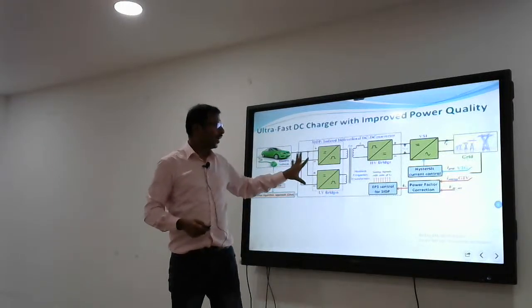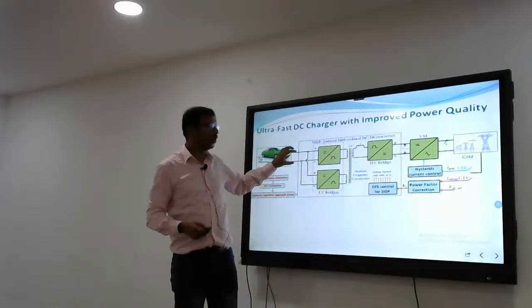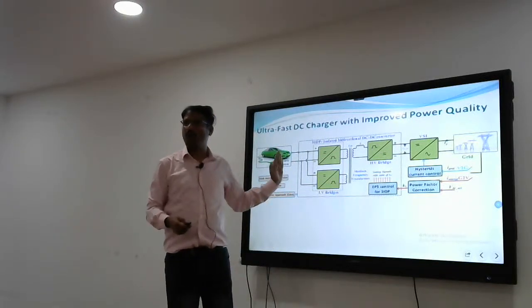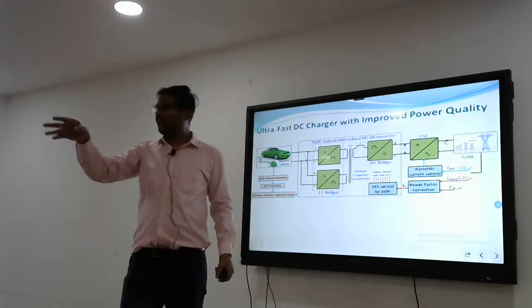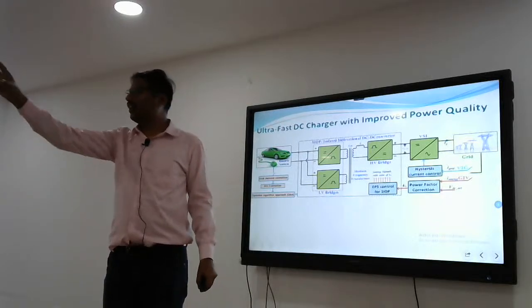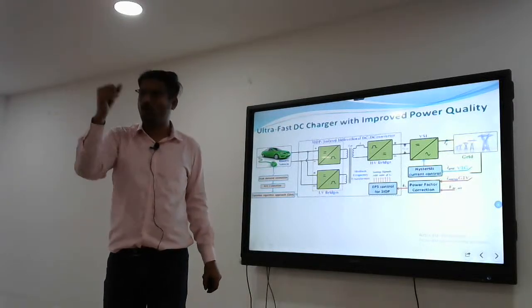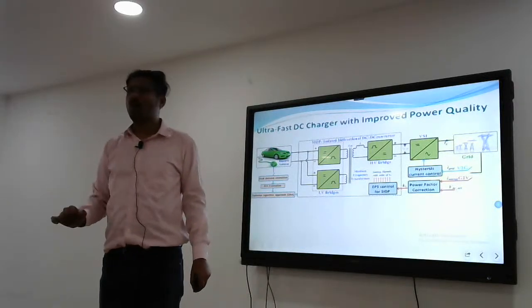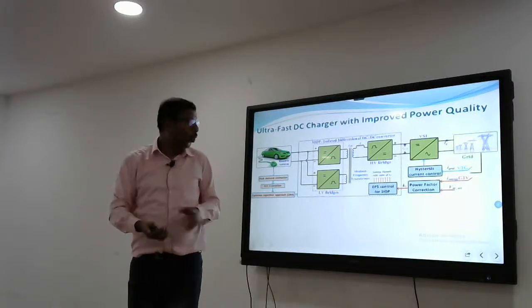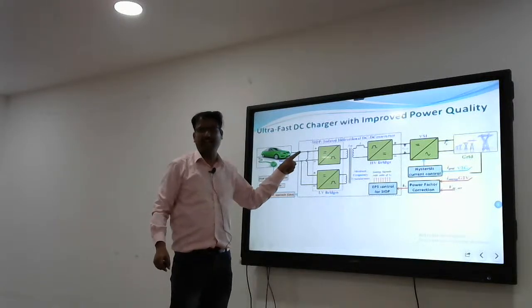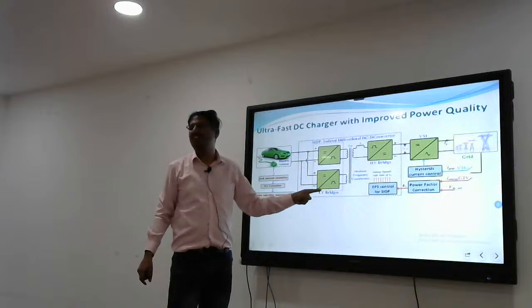This is actually such that one end becomes high voltage, the other end becomes low voltage, but current will be more. I told you one thing: even with a 48 volt battery, if you want to inject 1 kW power, what is the current? 20 ampere. If it is 10 kW, what is the current? 200 ampere — and 200 ampere has to go inside. I agree the battery will accept it, but your converter will not accept it.